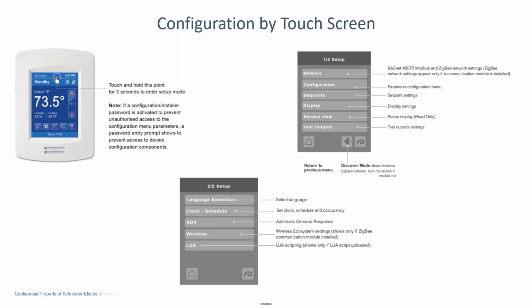Configuration is where you'd go to change, whether it's a rooftop unit or a heat pump, whether it's staged heat or modulating heat, whether it's a 2-pipe or a 4-pipe type of fan coil unit, whether it's a pressure dependent or pressure independent type controller. The set points functionality does all the set points: occupied, unoccupied, standby set points. Display is for all those things in the display: background color, what buttons you want to show up, how you want the arrangement to be shown on the screen.